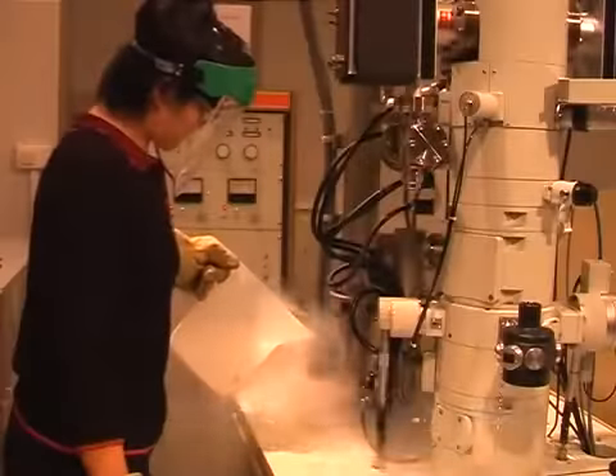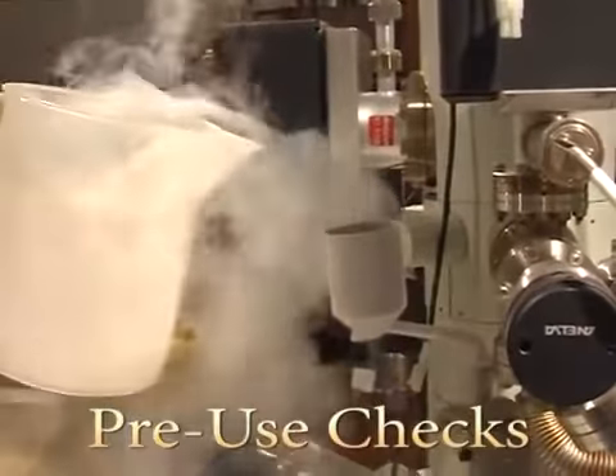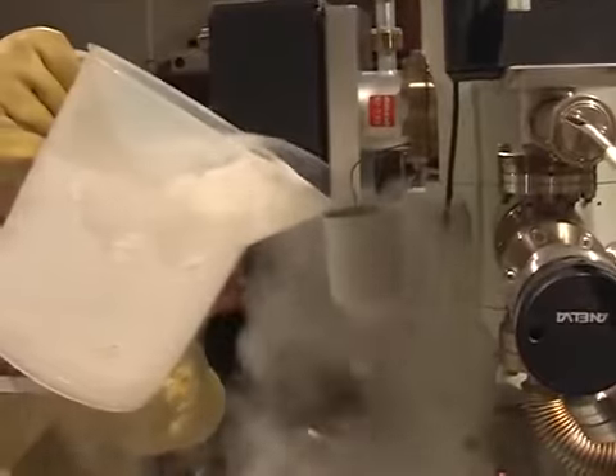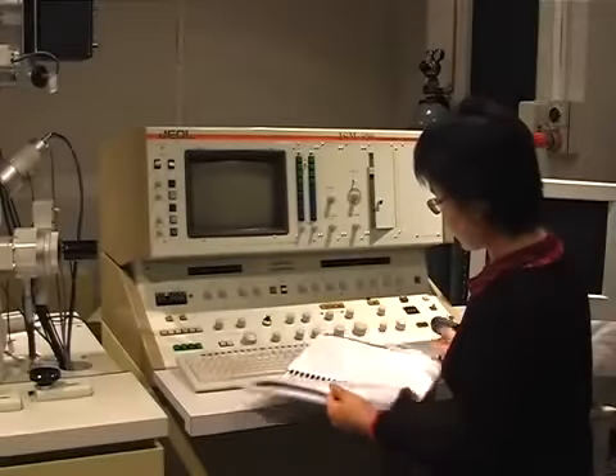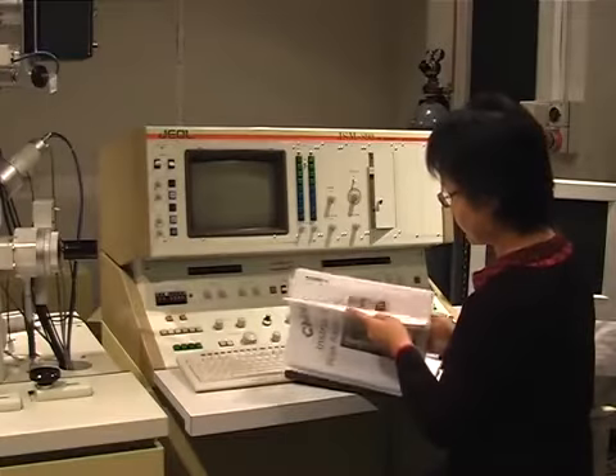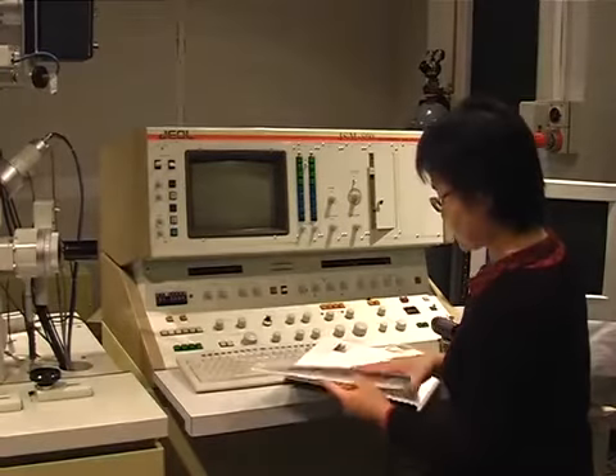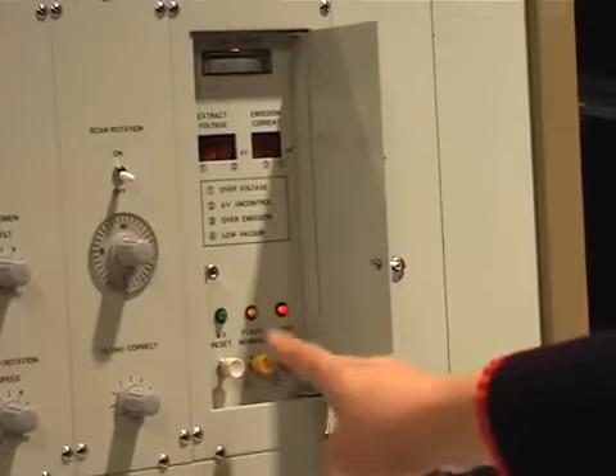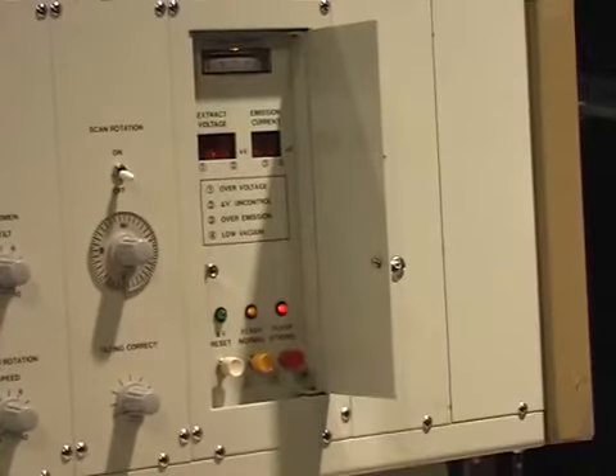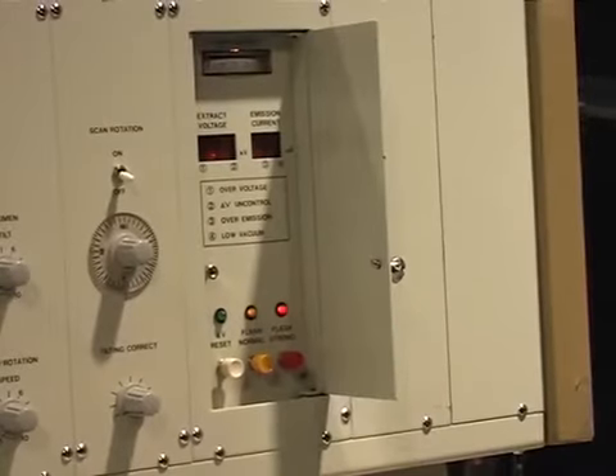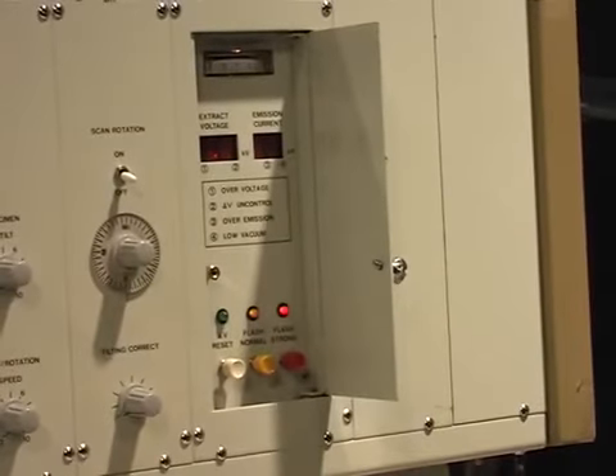To begin your SEM session, fill the DP cold trap and the cold finger dewar with liquid nitrogen. Using the instructions manual, check for risk assessment updates and that you've signed off on these. Follow the instrument manual carefully. Check the FE operation unit. If the flash normal and flash strong lamps are lit, seek assistance from CMM staff.